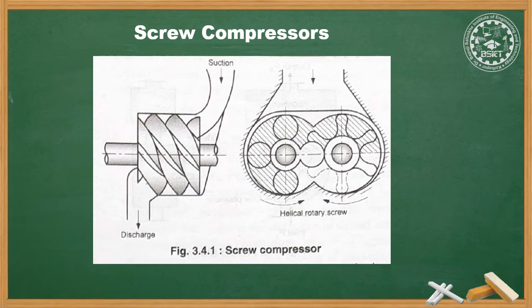The advantages of screw compressor are: it is less maintenance due to fewer moving parts, it is having low weight and smaller size, less starting torque. The disadvantage is performance is affected by the moisture present in the suction air.